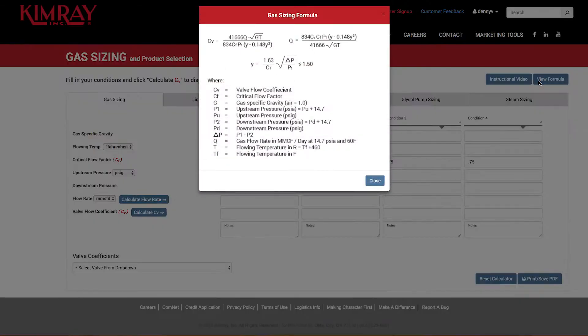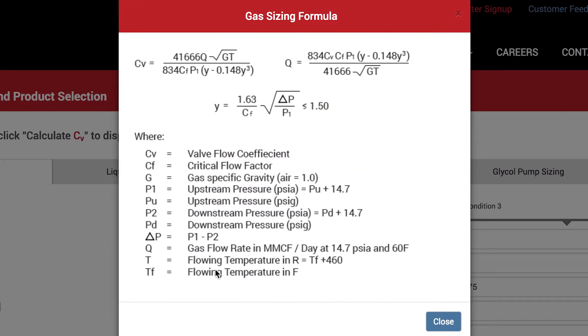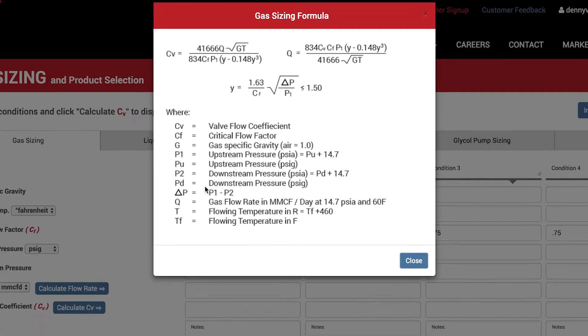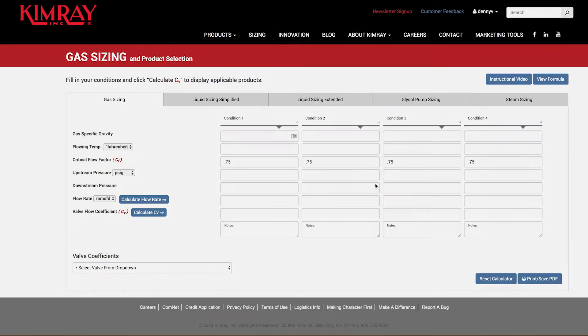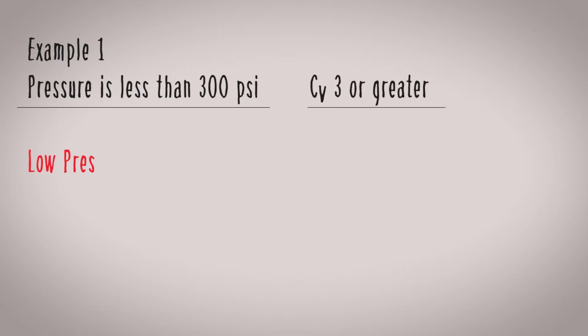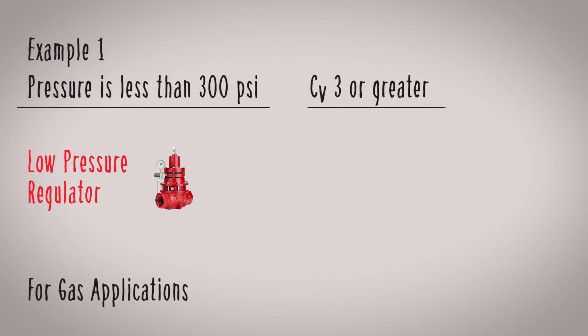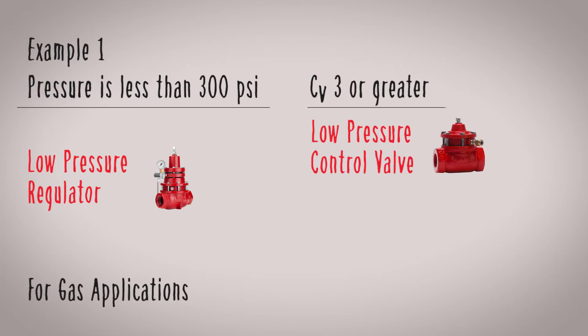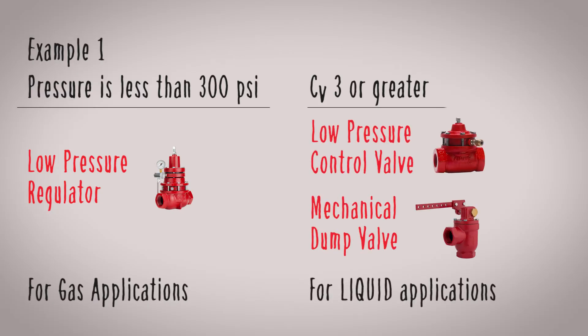To calculate your CV, you need to plug your conditions into the Kimray sizing calculator — we'll put a link in the description below. Let's look at two examples. In example 1, your pressure is less than 300 psi and your required CV is 3 or greater. In this case, a low pressure regulator should work for a gas application, while a low pressure control valve or a mechanical dump valve will work for a liquid application.